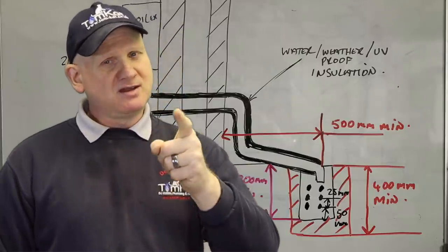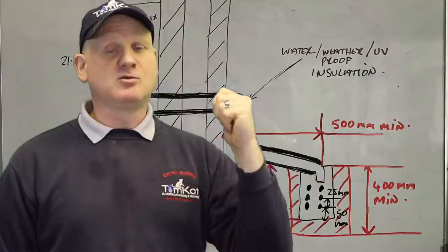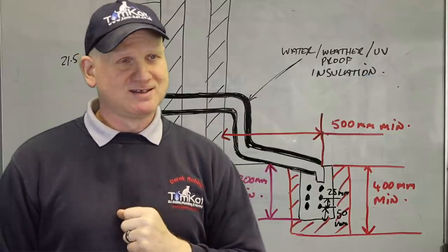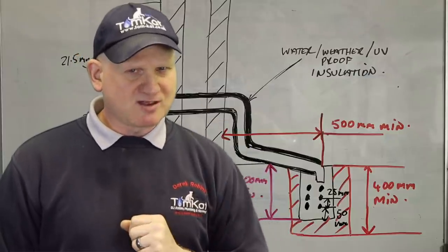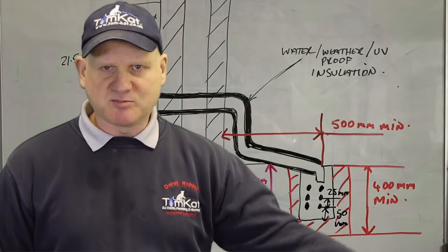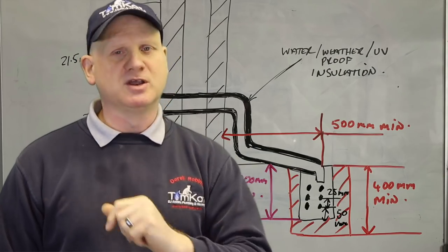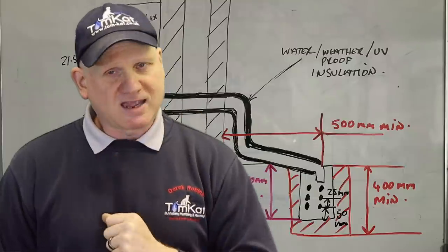But remember, when you're servicing a boiler where it's got limestone chippings, you need to check the limestone chippings every year to make sure they've not all disappeared, because otherwise you're just going to be putting acidic water back into the ground.